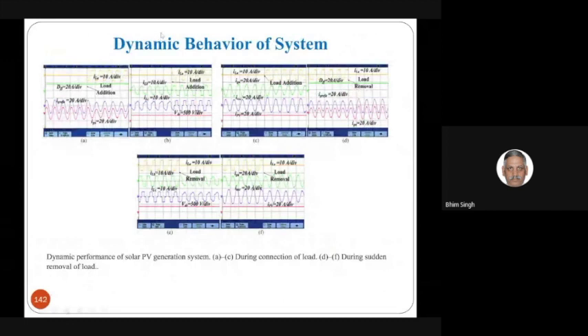So you can clearly see the performance when you apply the load, how the grid current changes. Grid current typically reduces because the solar power generation was constant, so some power goes to the load and less power goes to the grid. That's why the grid current is reduced. Similarly, when the load is removed, less power is consumed by the load, so more power goes to the grid and the grid current increases.